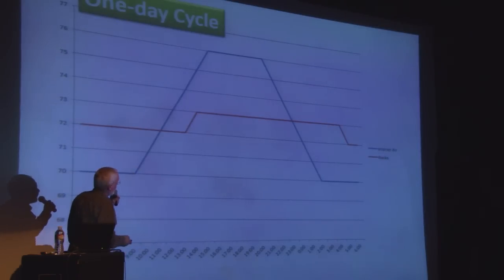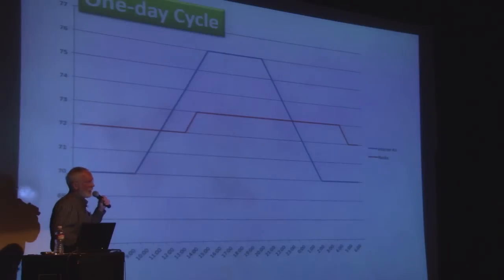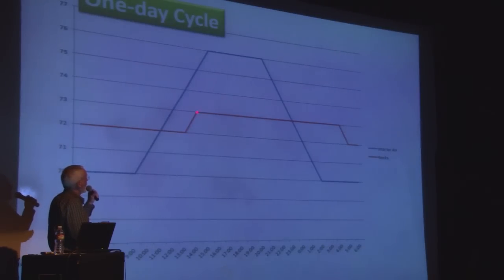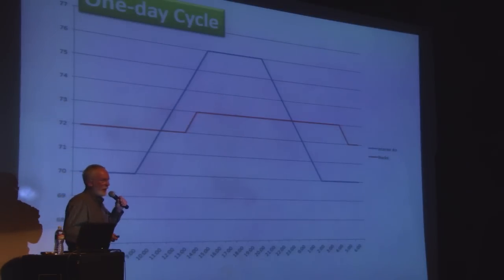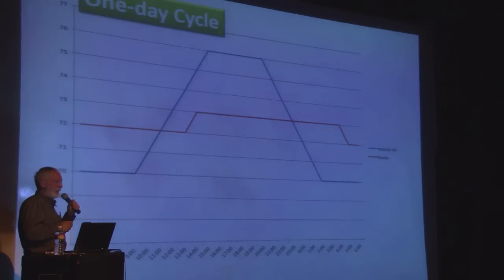The same thing when it cools off. If you set your thermostat to kick on at 70 as soon as you hit 71, because you want your house to stay at 72 degrees, so the heat kicks on here, you're not letting the thermal mass work. And you're not going to get the heat out of it, because if the air temperature is just trying to equalize and our thermal mass is only changing a degree or two, and our thermostat's kicking in here, we're not utilizing that mass. Okay? That's real important, because if you're testing a house that has thermostats with a close setting on it, you won't see the value from the thermal mass. You've got to let it do its thing.